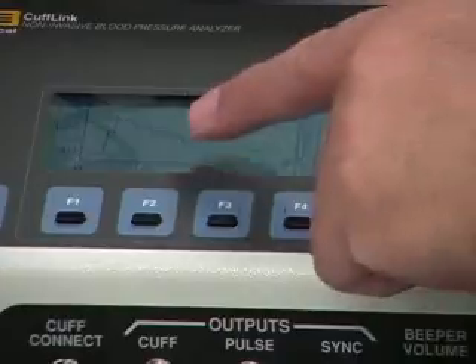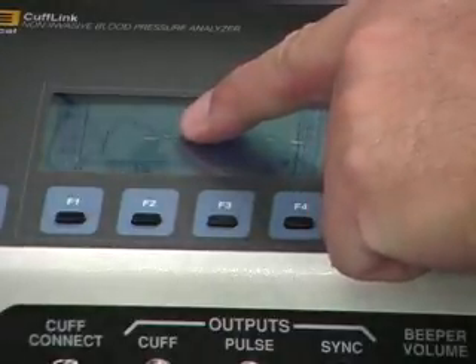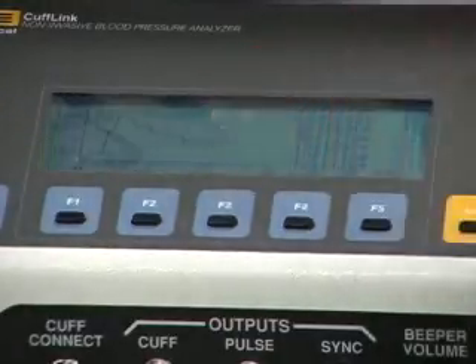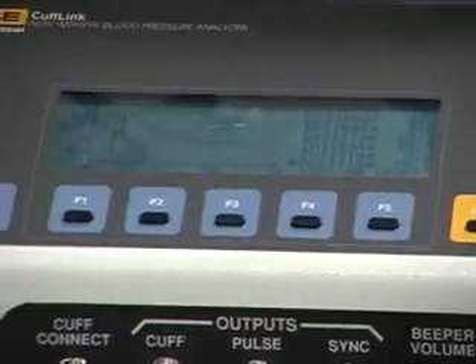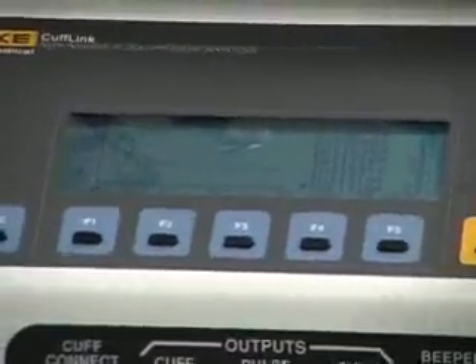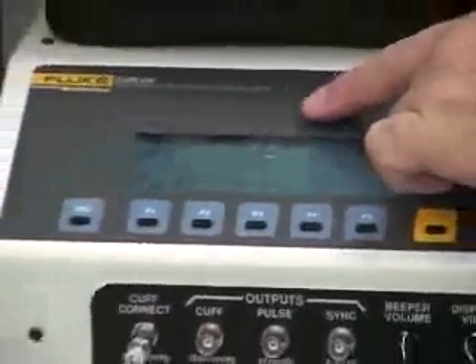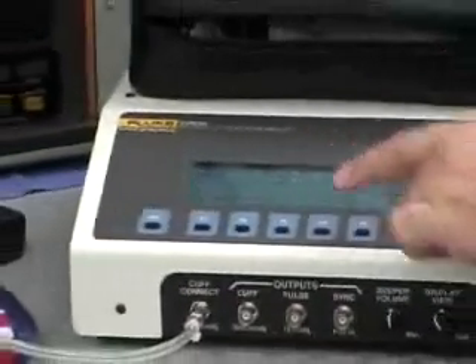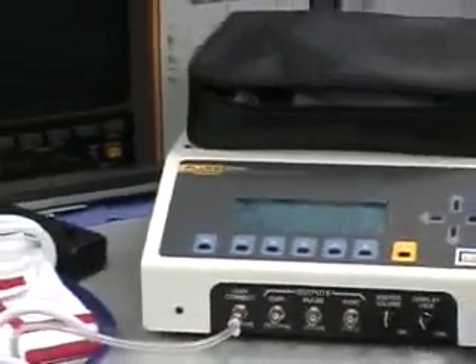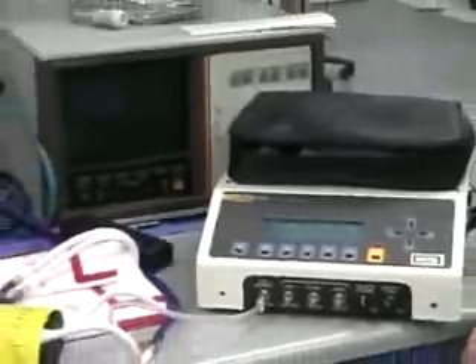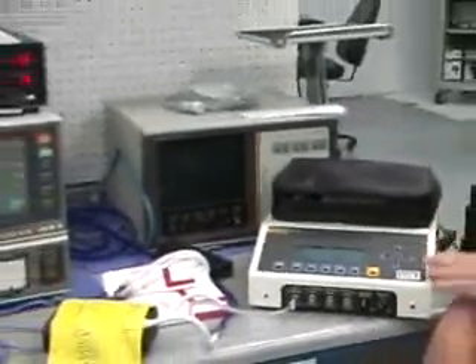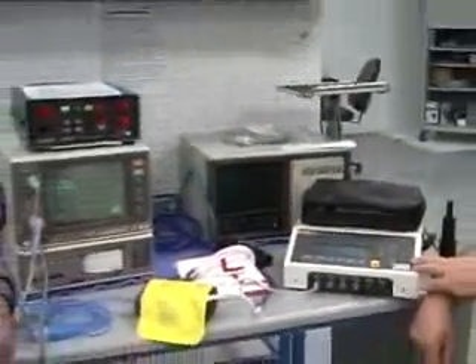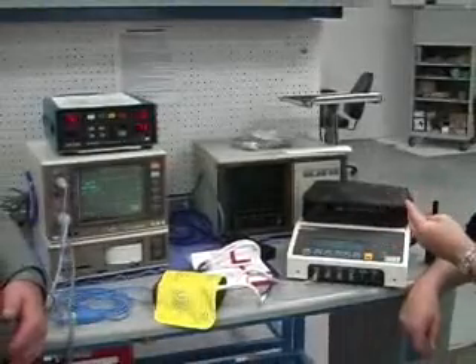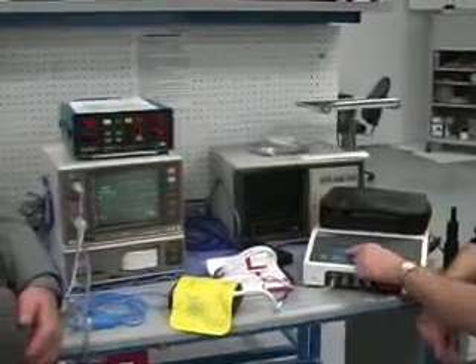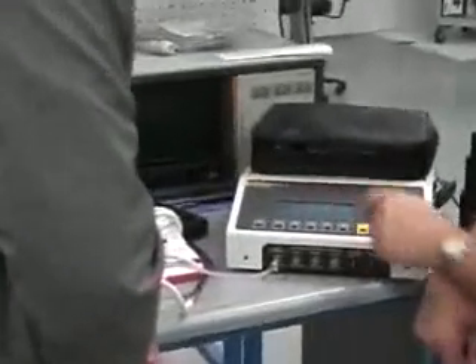And as you can see, the steps are much longer. Yes, you're right, because it says, hey, what's going on here? But this is the nice part about the Cufflink. You have that cuff pressure waveform, and you can say, well, yeah, it's a weird beat, it's an arrhythmia. It'll still measure it, but it's going to take longer because of that irregularity. And you can see the irregularity in that cuff deflation curve.